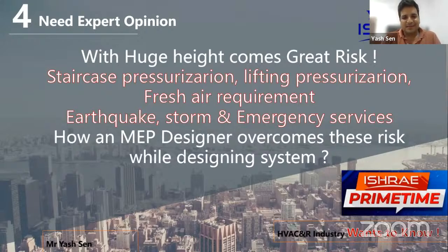For that, I suggest we can use MVHR, mechanical ventilation heat recovery. This system has a heat exchanger inside it, so we can take both sensible and latent load into consideration when designing the system. This system gives energy efficiency and is good for occupant health - they will feel comfort there. This is how we should think about fresh air requirements.